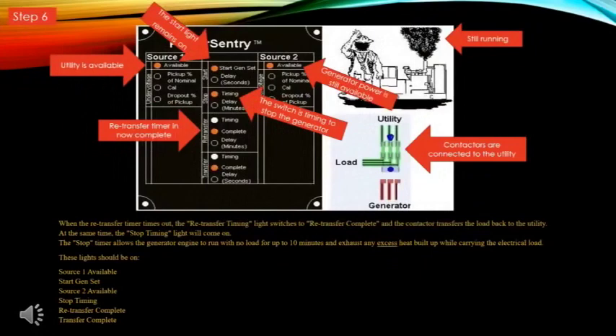Step six: when the retransfer timer times out, the retransfer timing light will switch to retransfer complete and the contactor transfers the load back to the utility. At the same time, the stop timing light will come on. The stop timer allows the generator engine to run with no load for up to 10 minutes and exhaust any excess heat that has built up while carrying the electrical load. Utility available is on, the start light remains on, the generator is still running, the retransfer timer is now complete, the switch is timing to stop, and the contactors are connected to the utility — shown in green.